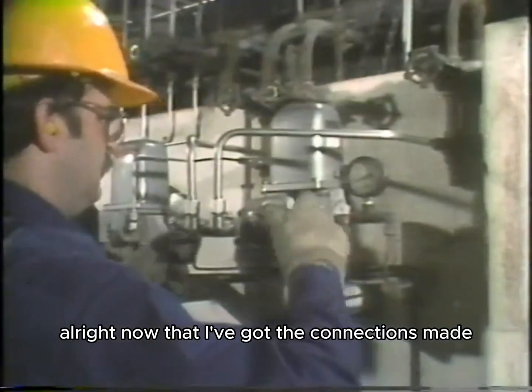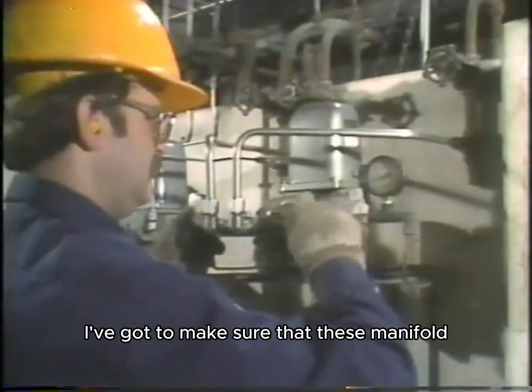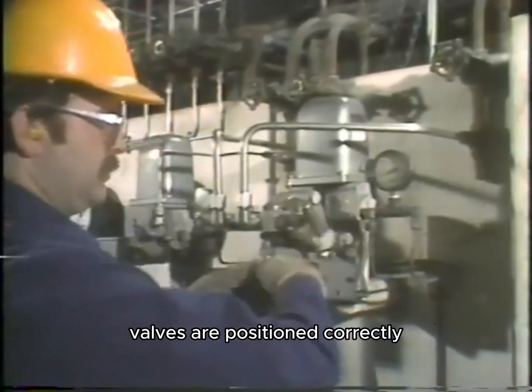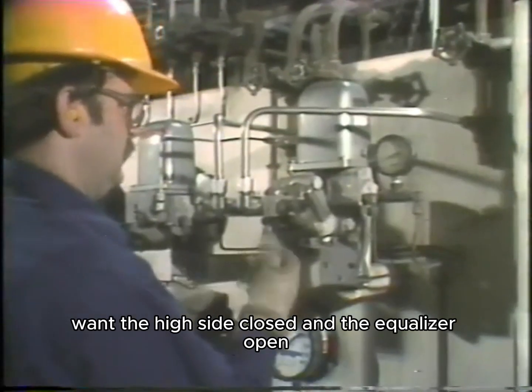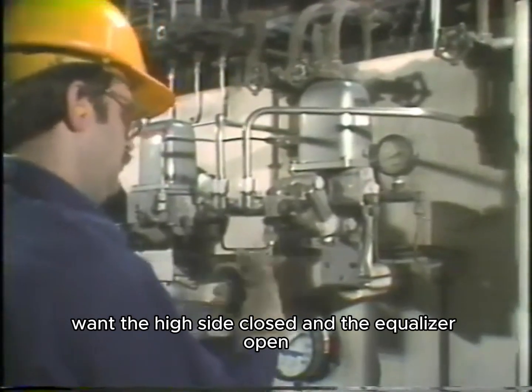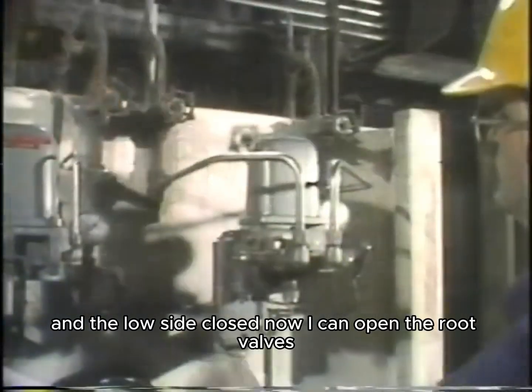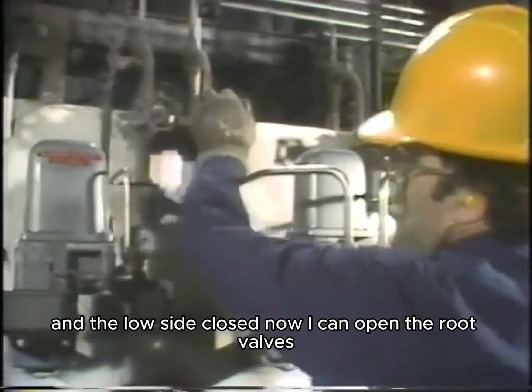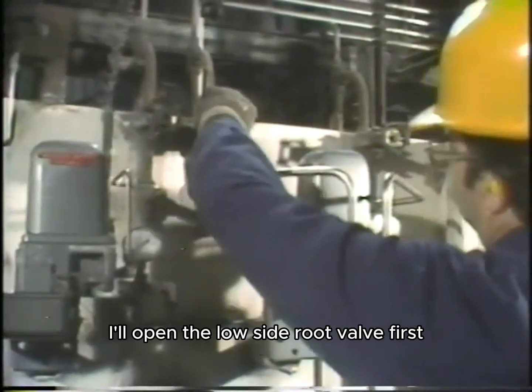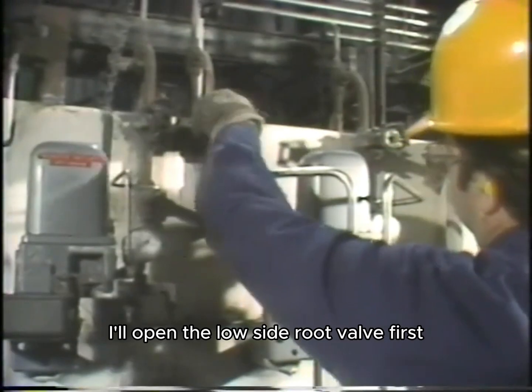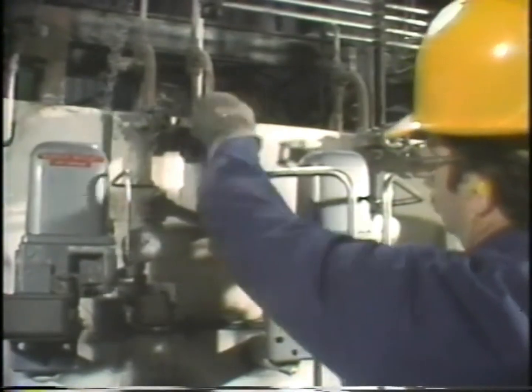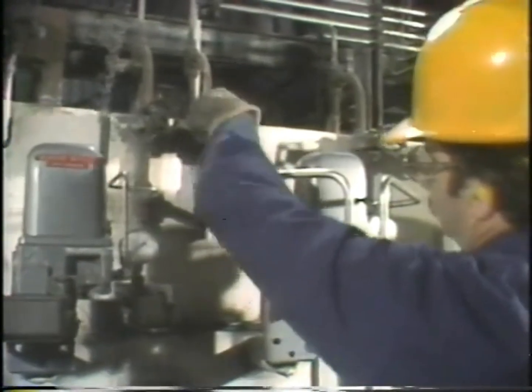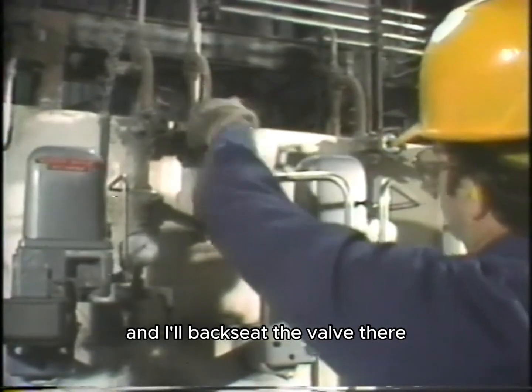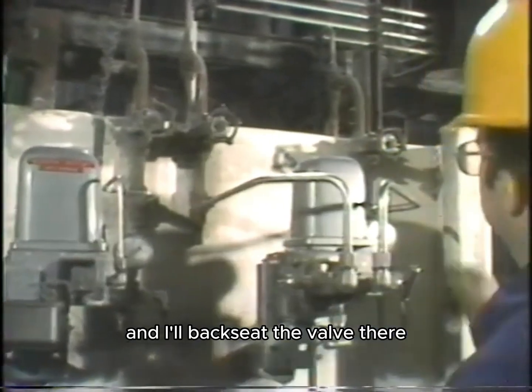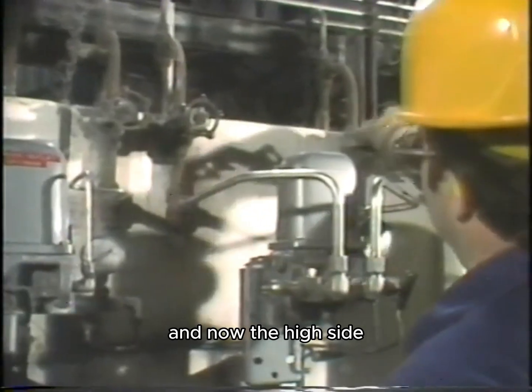All right, now that I've got the connections made, I've got to make sure that these manifold valves are positioned correctly. I want the high side closed and the equalizer open and the low side closed. Now I can open the root valves. I'll open the low side root valve first. And I'll back seat the valve. There. And now the high side.